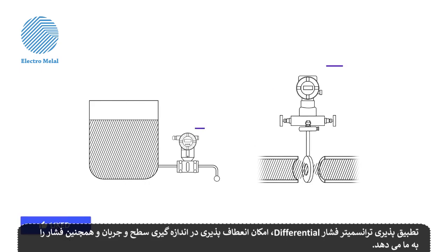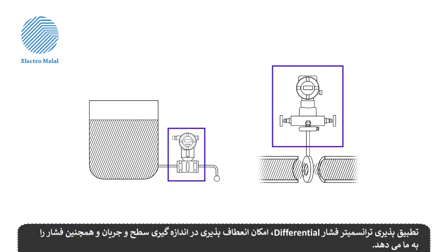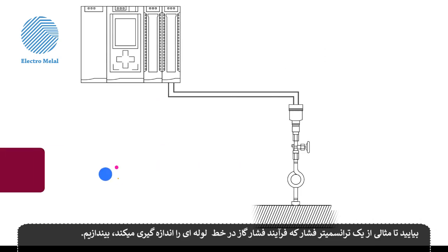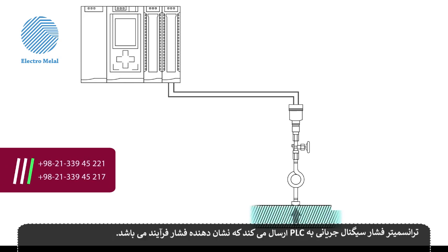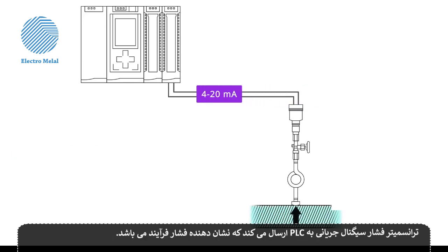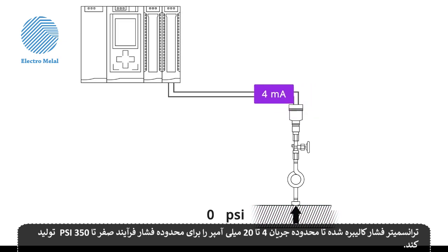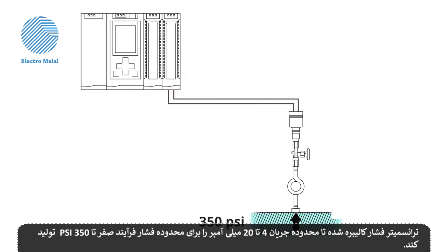The versatility of a differential pressure transmitter gives us the flexibility to measure level and flow as well as pressure. Let's have a look at an example of a pressure transmitter measuring process pressure of gases in a pipeline. The pressure transmitter will send a current signal to the PLC, which represents the process pressure. The pressure transmitter is calibrated to provide a current range of 4 to 20 milliamps for a process pressure range of 0 to 350 PSI.